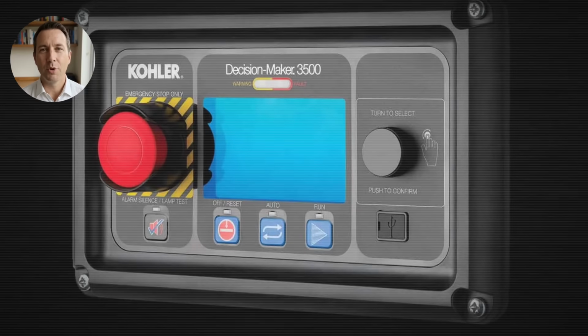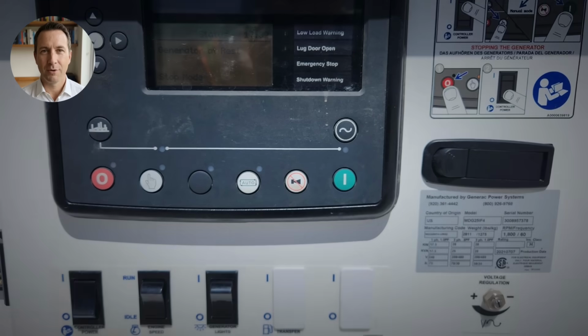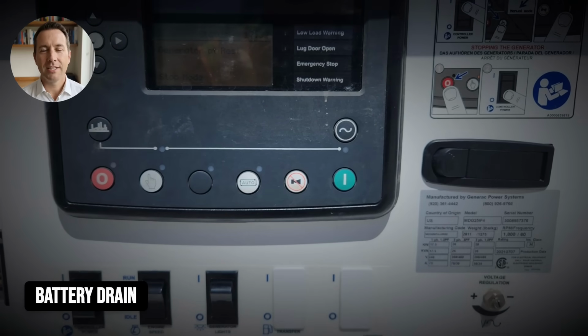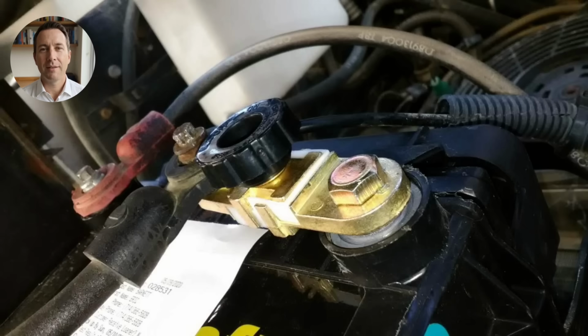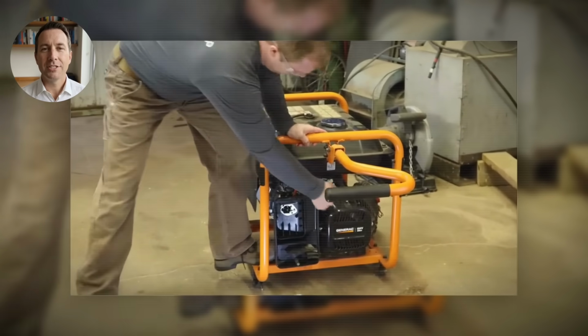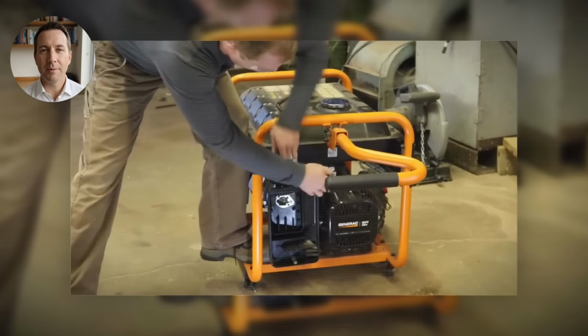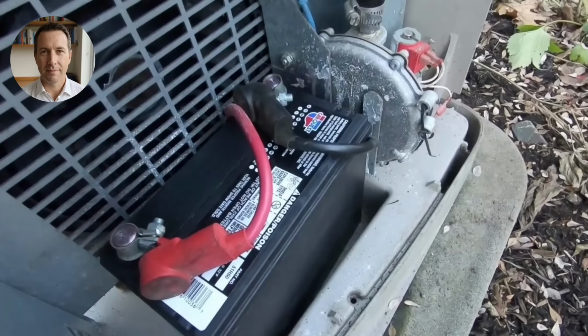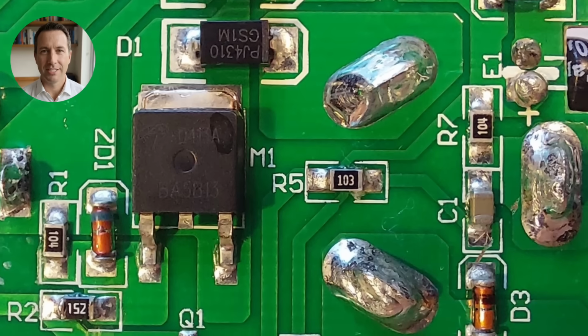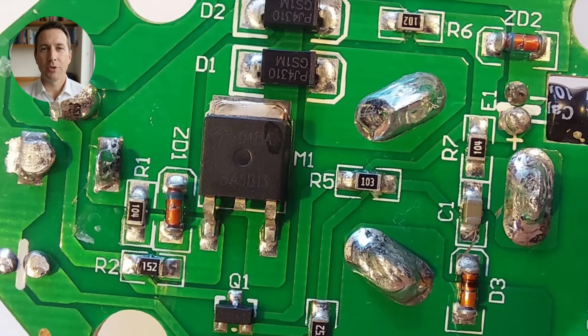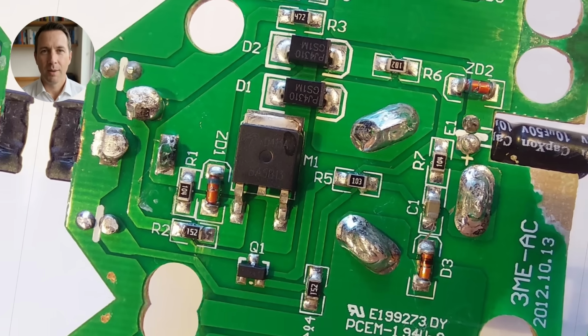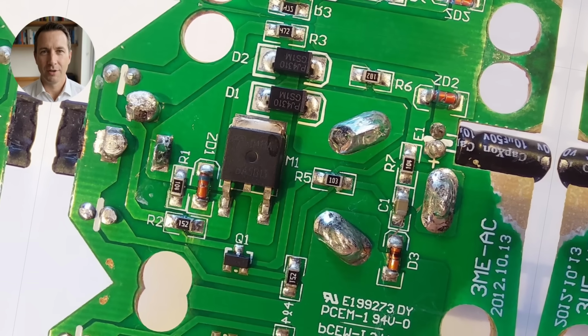Then there's a failure mode that's almost invisible. The battery charger circuit is integrated into that same controller. When it fails, your starting battery quietly drains over 1 to 2 weeks, and the generator silently becomes unable to start. Multiple homeowners reported replacing batteries 2 and 3 times before someone finally diagnosed the actual problem, which was the charger circuit on the control board.